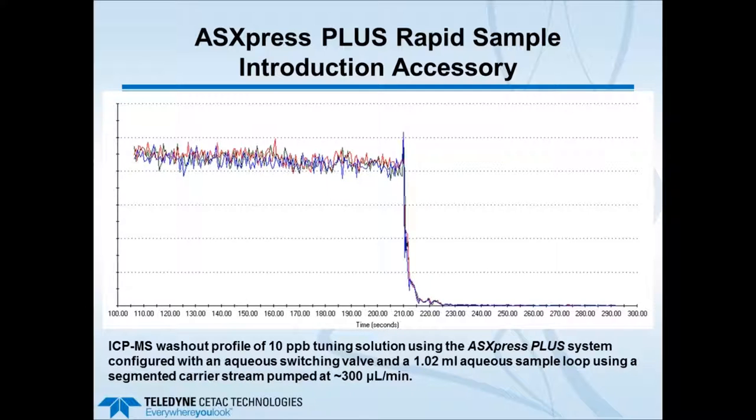The next slide shows the washout profile of the same tuning solution using the same volume sample loop at the same speed, but now with air pockets going into the carrier solution. The air pockets segment the carrier liquid into discrete liquid pockets, preventing diffusion of the analytical sample back into the carrier liquid. The air pockets act as a buffer, producing a much more rapid and sharp drop-off in analyte signal. This is a key point in getting the best washout times with the ASXpress Plus.